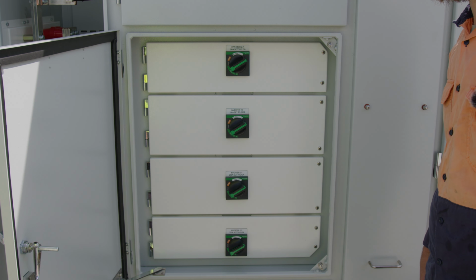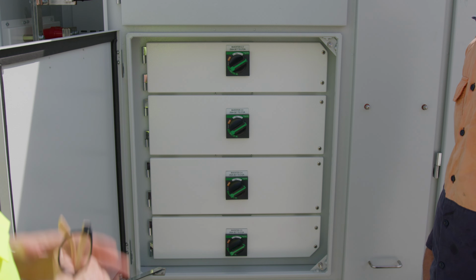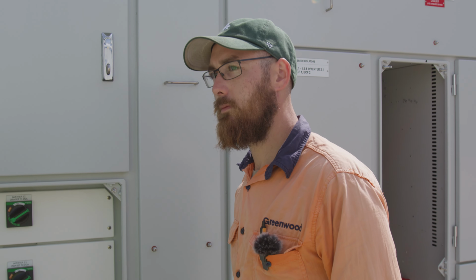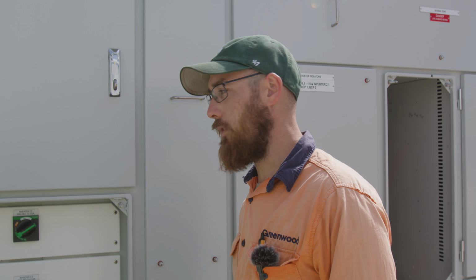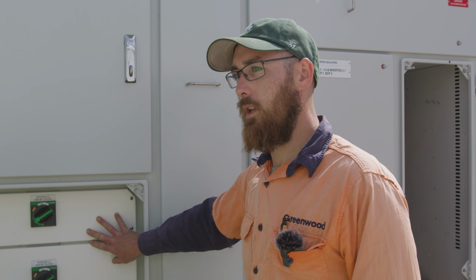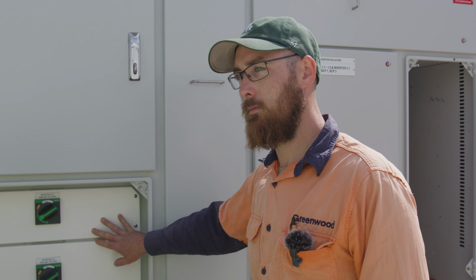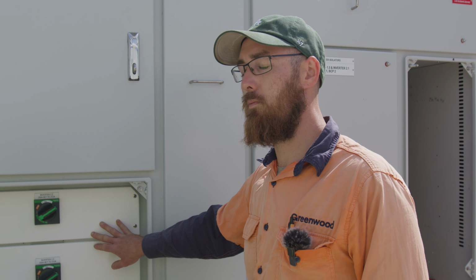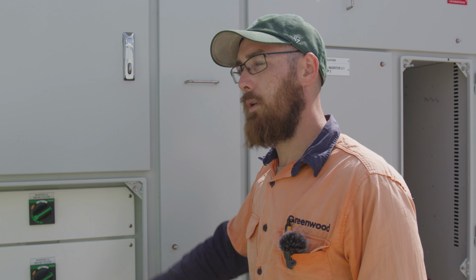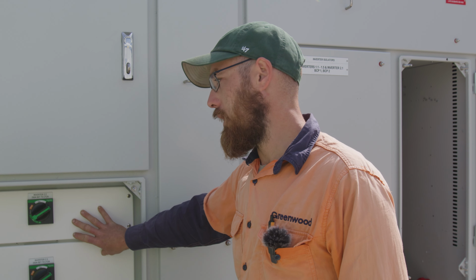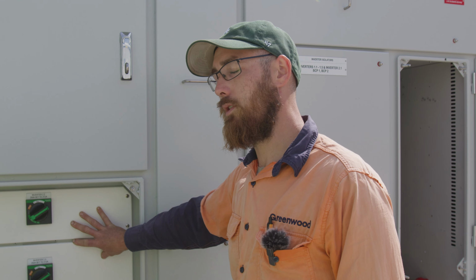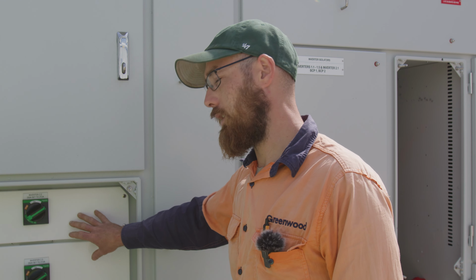So can you quickly, for the people who don't know, explain the difference between an isolator and a circuit breaker? An isolator has the capability of disconnecting the load at a specific current. So they've got 250 amp isolators inside each inverter. If you do turn it off, it will disconnect the load. However, the circuit breaker gives you short circuit and overload protection, which an isolator doesn't do. It has the capability of manually being switched to disconnect the load, but it won't do it automatically. Whereas a circuit breaker has thermal strips inside that once they get to a certain temperature, trigger a spring that disconnects the load.